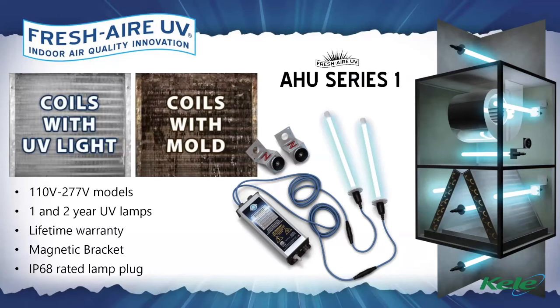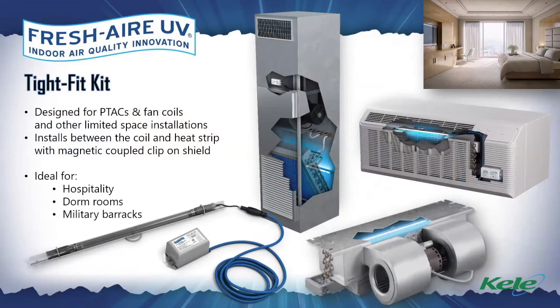The systems themselves have IP68 rated plugs, which means that typically what will cause an issue for a UV lamp is moisture penetration. And because our lamps are watertight, we don't have those issues. The power supply is available from 110 to 277 volt. Again, a really refined product that makes it easy to start implementing UV for your own facilities or for your customers. The system also has, as I mentioned earlier, a lifetime guarantee, and that's common across the Fresh-Aire UV line.